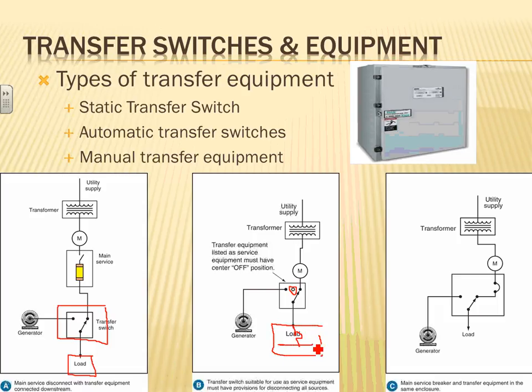Have you guys designed anything like this? Landing it into the, and then you bond the neutral to the ground right into the service disconnect means, which is now the auto transfer switch. That's backing up the whole building.